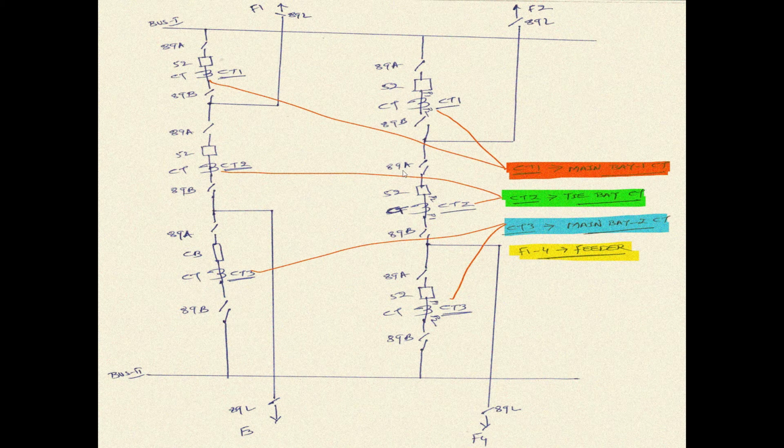Basically, the P1 and P2 sides of the CT depend upon the CT erection during the initial erection works inside the substation. So we don't have any control over this P1 and P2. That is, on which side you will see the P1 and on which side you will see the P2, that purely depends upon the initial erection of the instrument transformer in your switchyard.